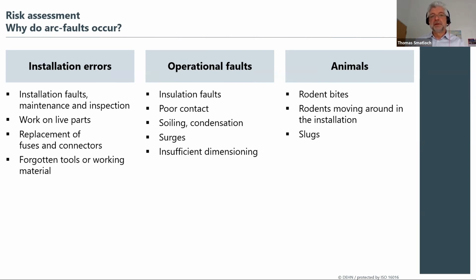Operational faults are typically insulation breaks, poor contacts, condensation, surges even, so voltage peaks from the grid, or insufficient dimensioning. From the animals, rodent bites, of course, what we have in Europe. Actually, I've seen interesting pictures from my Indian colleagues.